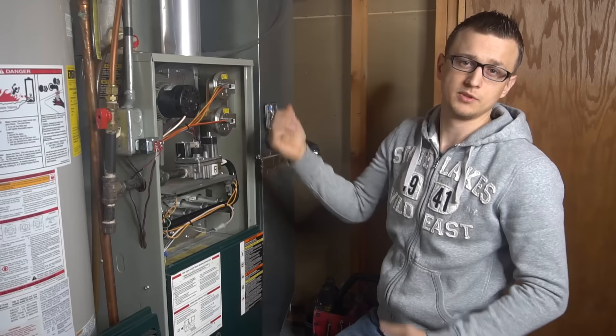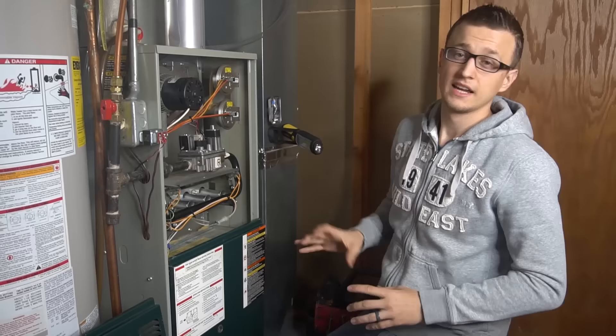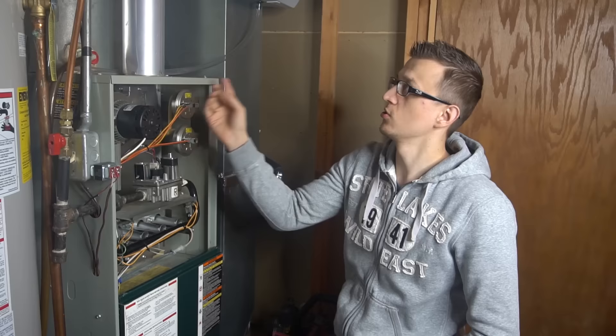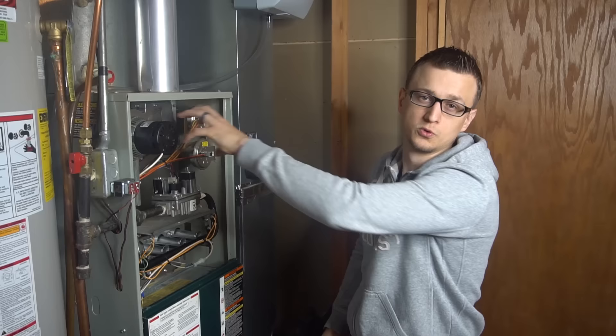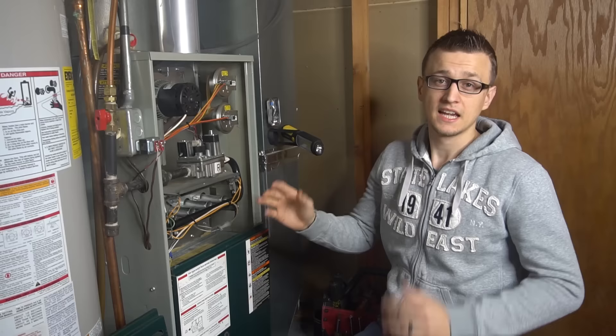You need to clear that blockage out or hire somebody to do it for you. If you put that door back on while the furnace is running and everything extinguishes, that means for sure the pipe is blocked. The exhaust pipe, which is usually hooked up to your inducer motor, doesn't get stuff inside it as often, but I have seen birds go down into that pipe. If they can't get out the other end, they usually end up in the inducer motor, and you'll hear some kind of a rattle when the inducer motor starts. Just take the inducer motor off and clear it out.